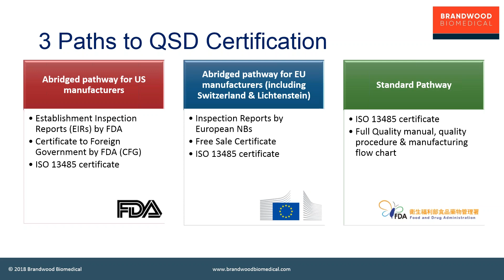If you do not hold a European or a US regulatory approval and quality certification, then there is a third pathway, which is called the standard pathway, where you submit an ISO 13485 certificate if you have it, plus your full quality manual, quality procedure and manufacturing flowchart, and that will be reviewed by the Taiwan FDA. If all else fails, you can, of course, submit to a direct Taiwan quality systems audit, but that almost never happens. Taiwan FDA doesn't usually audit outside of the country for medical devices. So these are the three ways forward.